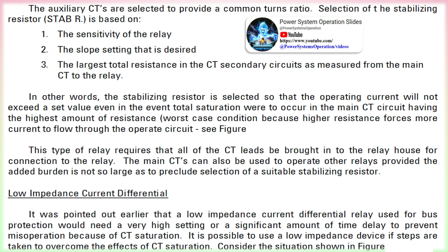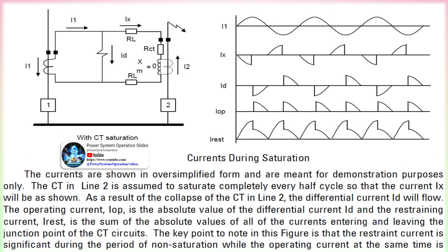Linear couplers, which have no iron in their core, can be used to overcome the problems caused by CT saturation. These devices have a linear characteristic that produces a voltage in the secondary that is directly proportional to the primary current. For an external fault, the sum of the voltages will be equal to zero or very nearly so, whereas the voltages all add together for an internal fault, thus producing sufficient voltage to operate the relay. However, linear couplers have not been widely accepted because of their special characteristics and limited application.